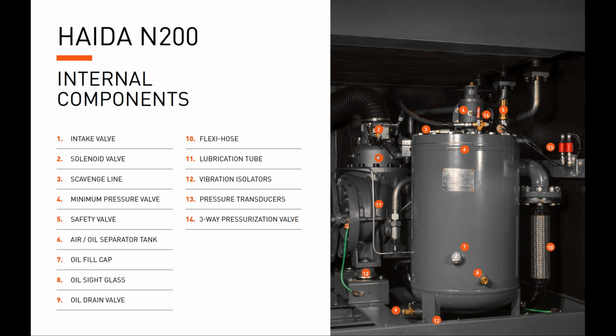So just going over again, the intake valve, there's the solenoid on the intake valve. Here you see the scavenge line, and the minimum pressure valve is located here. Safety valve for the air oil separator tank is here, which is mounted on the air oil separator tank.